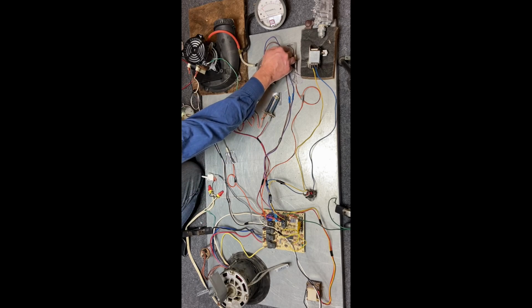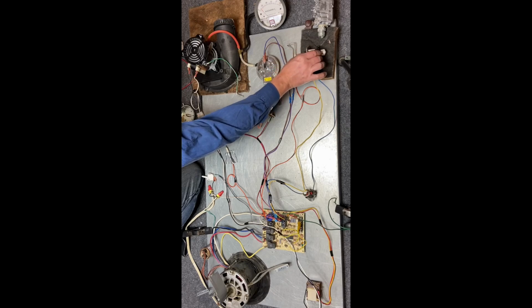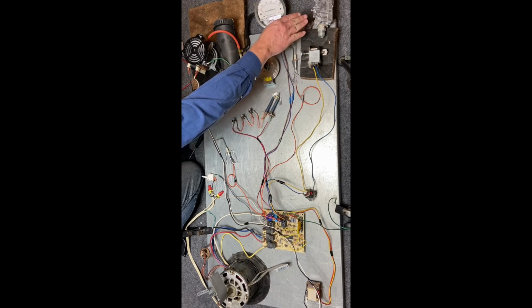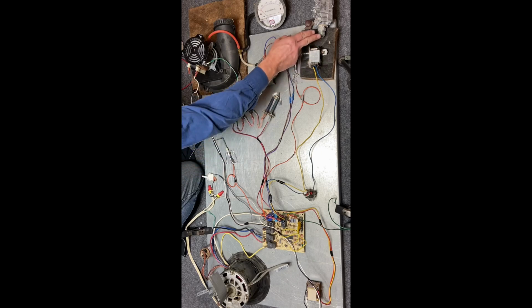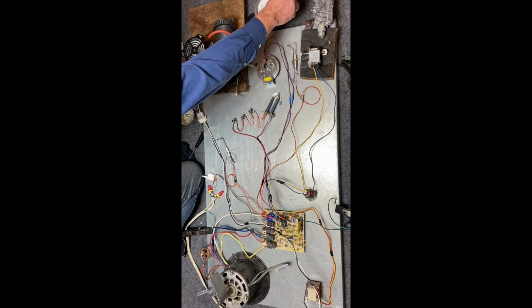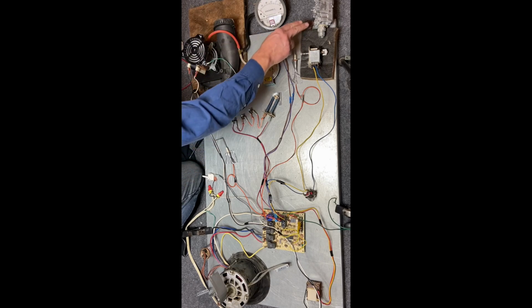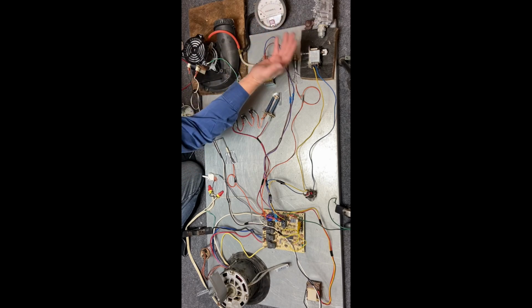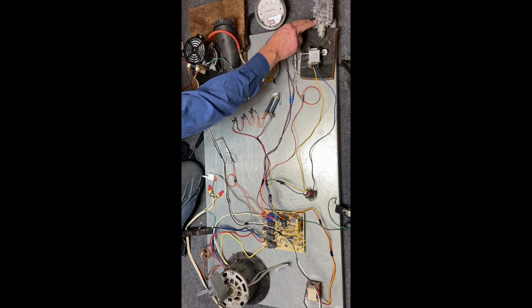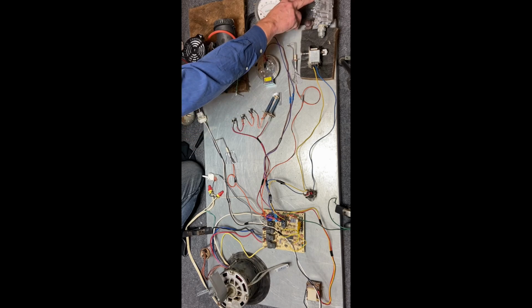You got to remember it's a combination of a solenoid valve, which is this, and the pressure regulator. The pressure regulator reduces the pressure coming in to the correct 3.5 inches of water column coming out for most natural gas furnaces. So you need to see, do you have pressure coming in? Maybe the customer didn't pay their gas bill. So do you have the correct pressure in? And also see if you have pressure coming out.